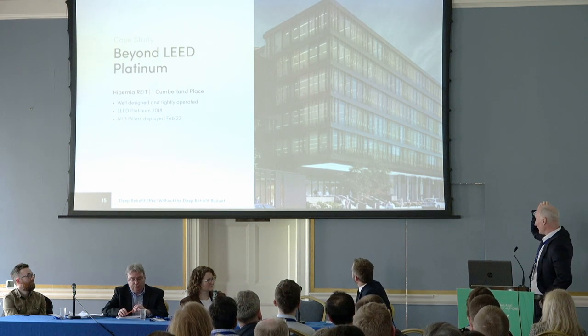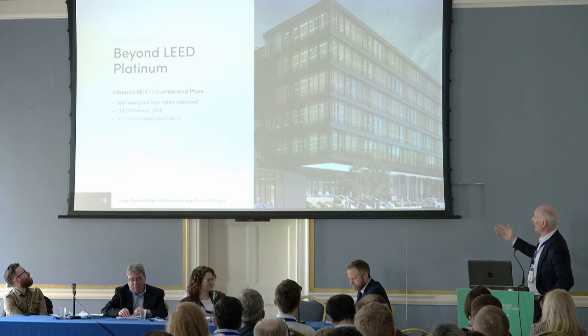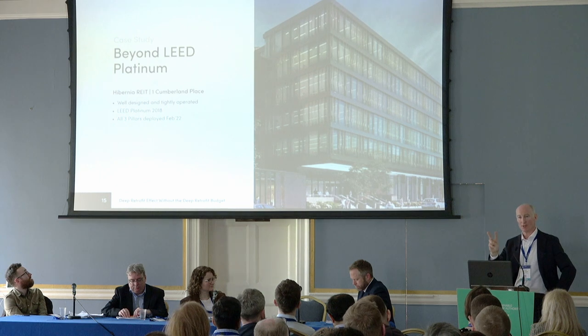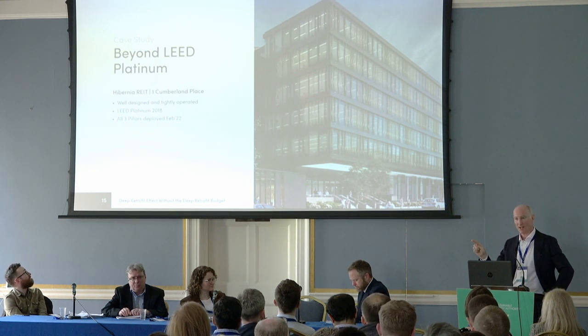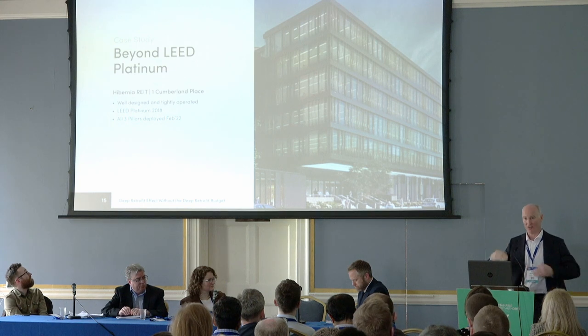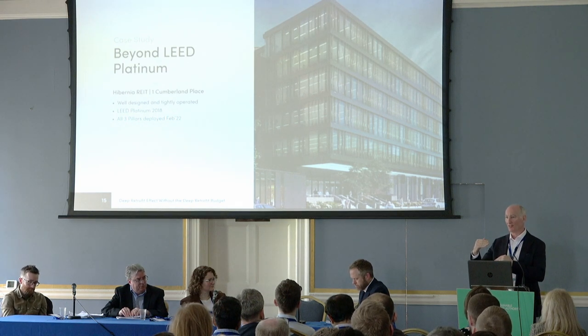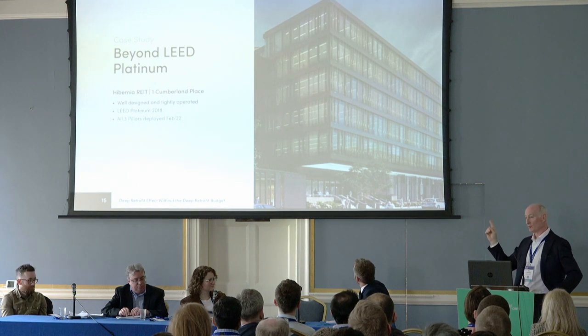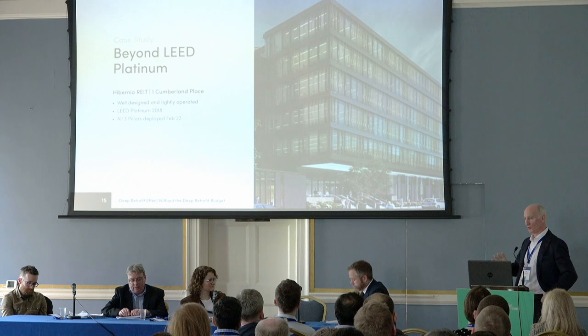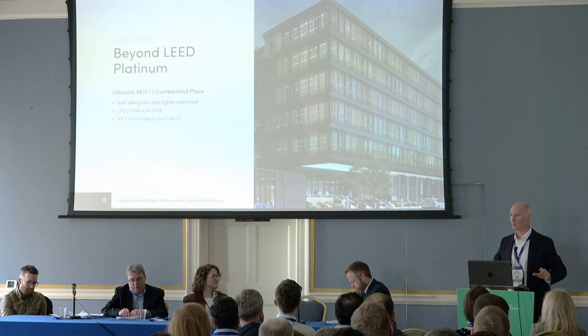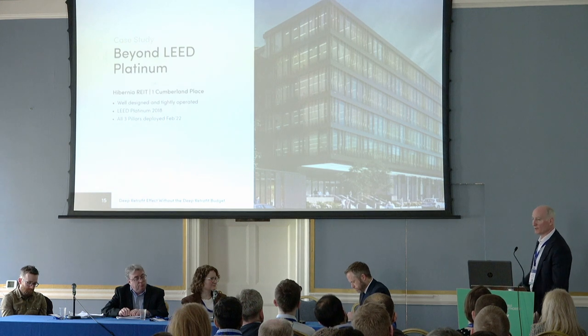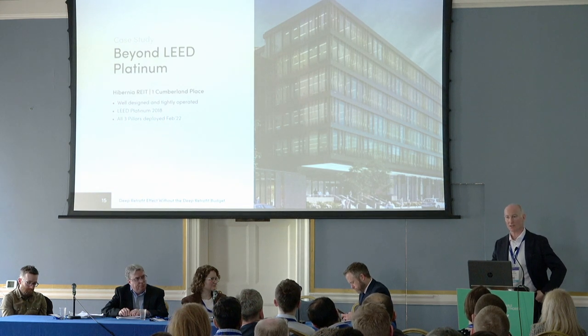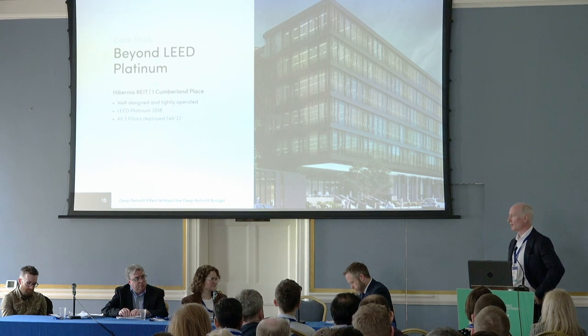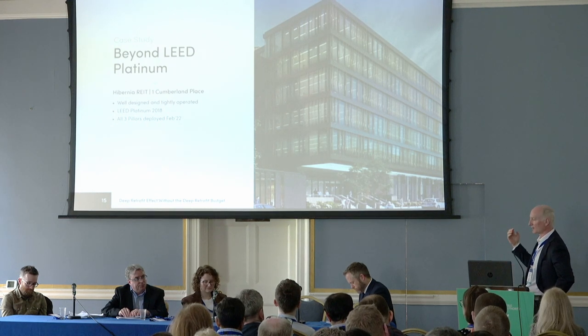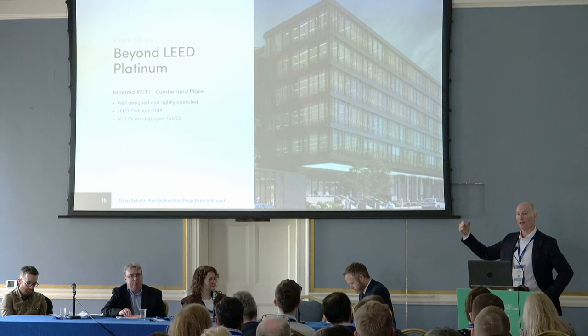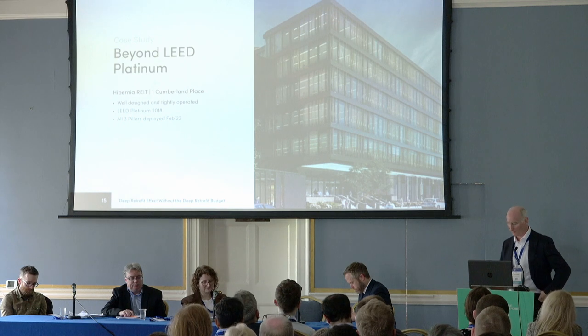This is a LEED Platinum building, a fabulous building, but the energy we've reduced in this building using the three-pillar approach—attacking those three challenges—if you were to offset that saved energy with PV panels on this building, you'd need 10 times the roof area to get the equivalent of the energy we've saved using this three-pillar approach. So if we didn't use the three pillars and wanted to reduce by that amount of energy, we'd need 10 times the available roof space. It's just not going to happen. So we really need to tackle the three pillars first before we get onto the solar, and then when the solar comes along, it'll be a higher proportion of what's remaining to be tackled. That's just an image to illustrate it.